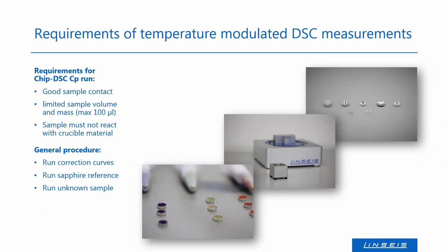And of course, a simple thing, the sample must not react with the crucible material. So I think that's clear. If you want to measure gallium, we need different crucibles than our standard crucibles made from aluminum. Of course, you can use alumina, or whatever crucible you can find here. And the general procedure is, at first we need the correction curve, the calibration curve, mostly made with a sapphire, and then of course we measure our unknown sample.